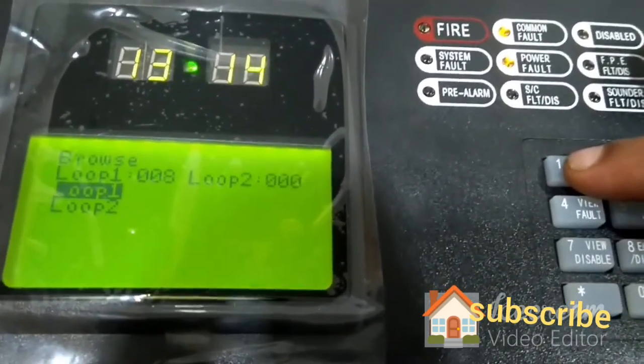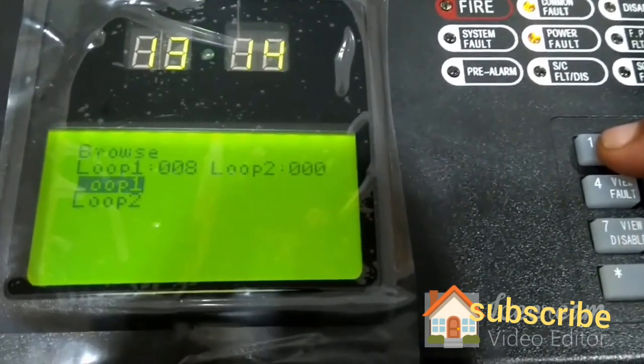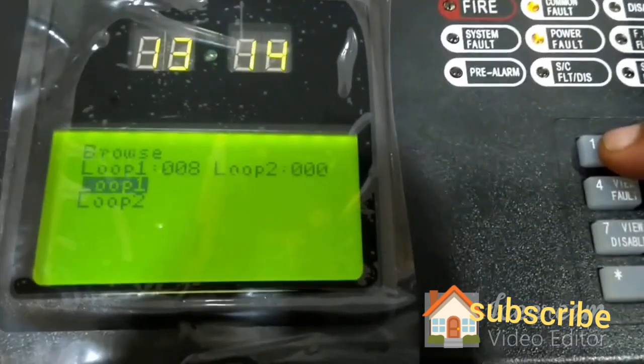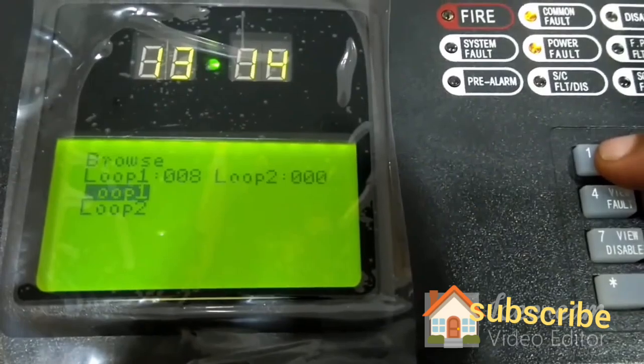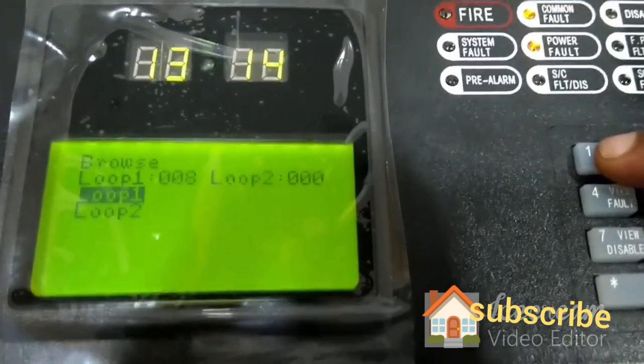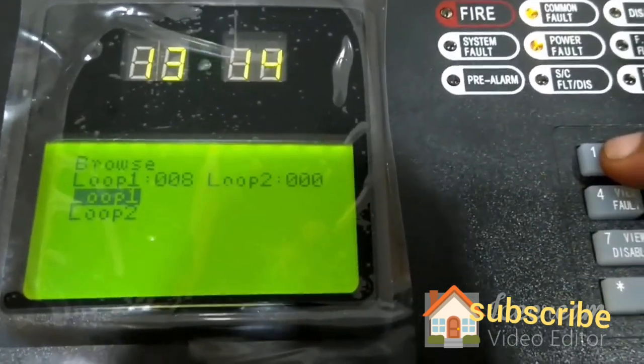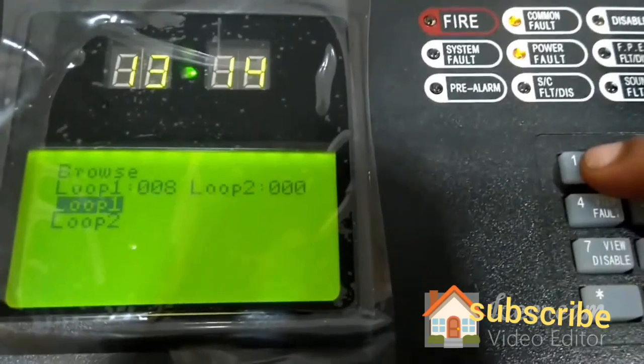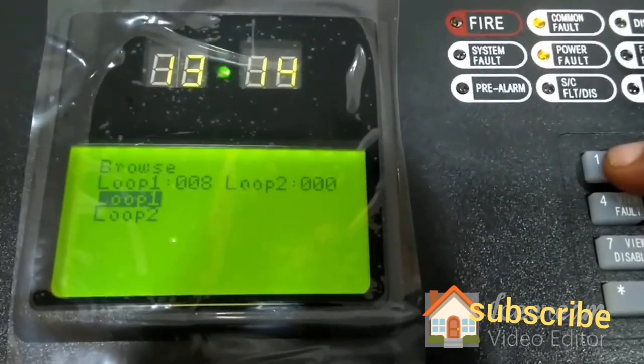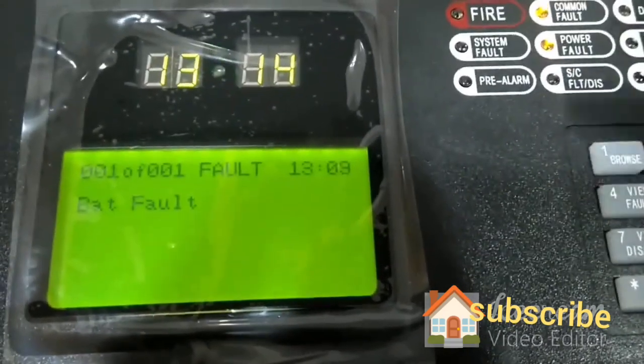In my case, I had connected 8 devices on loop 1, and loop 2 is not connected, so I got the total count. When you install, you should know the total number of devices connected on each loop, so that the count should match here. If it is not matching, we need to do the basic troubleshooting.